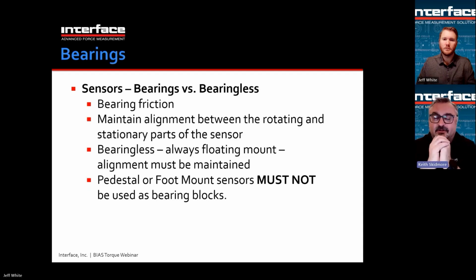Advantages of a bearingless sensor is there is no bearing friction, and we spelled bearing wrong here, seems, but anyway, bearing friction is something that, say you're trying to test a bearing and measure how much friction that bearing has under certain conditions, the bearing friction in the sensor might actually contribute, and you may not want that as part of your measurement. And so a bearingless sensor eliminates that.